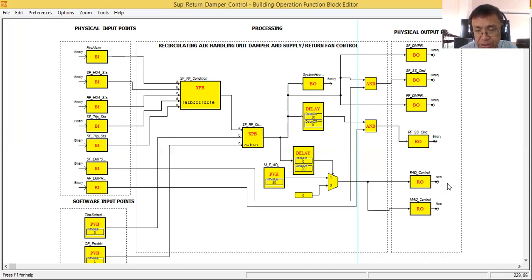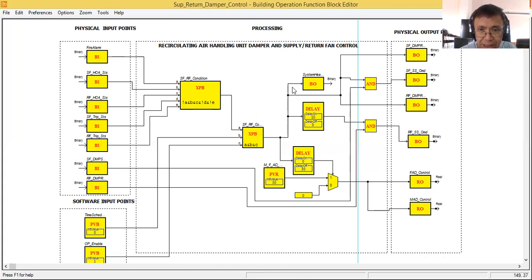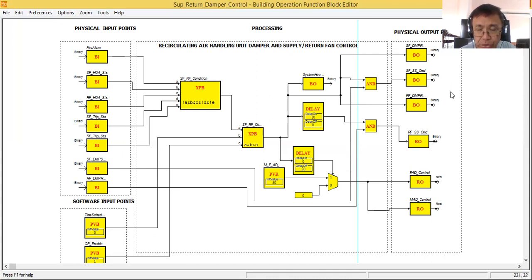The modulating damper actuator receives five volts and opens 50%. Likewise, the mixed air damper control also receives five volts and opens 50%. So initially both the fresh air and mixed air dampers open at 50%. Now for the supply fan and return fan damper — if the conditions are met, immediately the binary output gives a one signal connected to our IO module digital output, meaning the relay in the digital output is activated, then the normally open contact starts the supply and return fan damper.